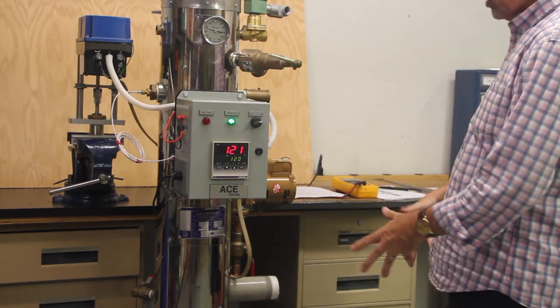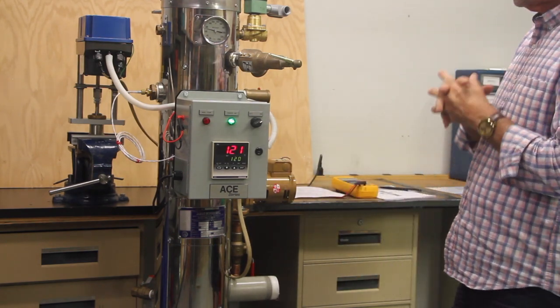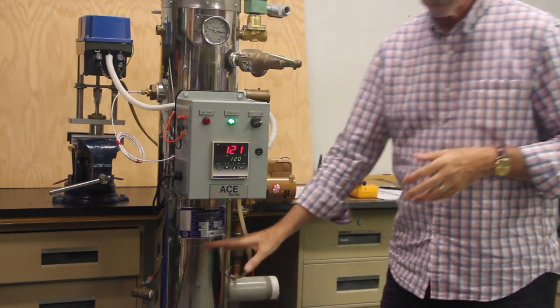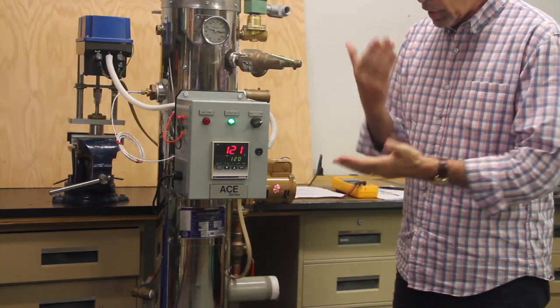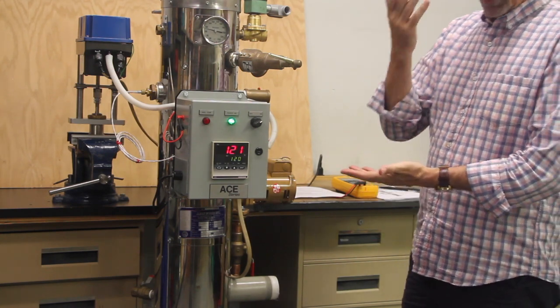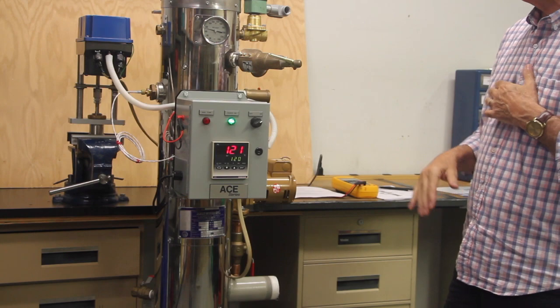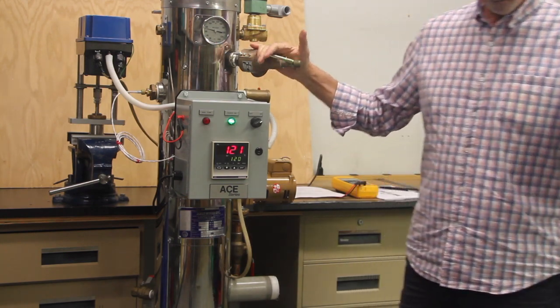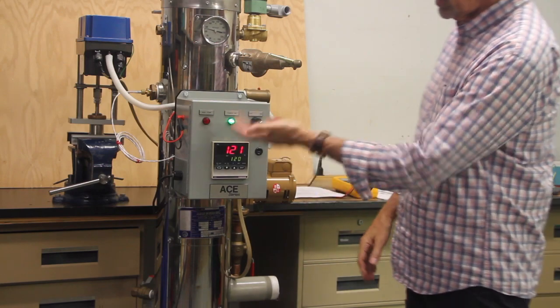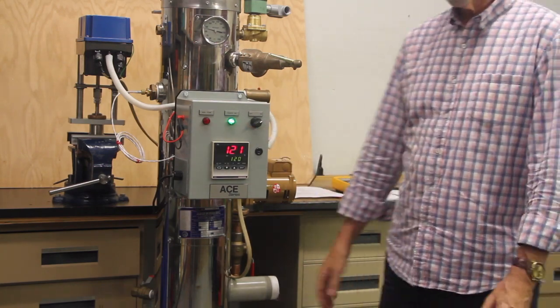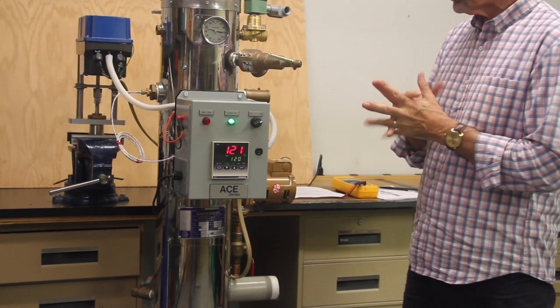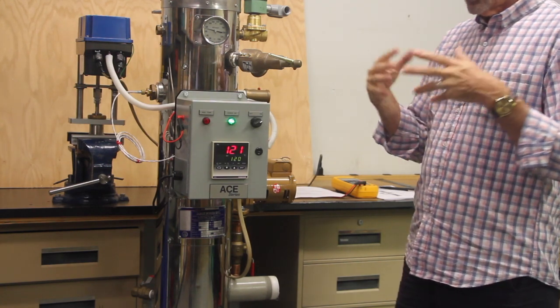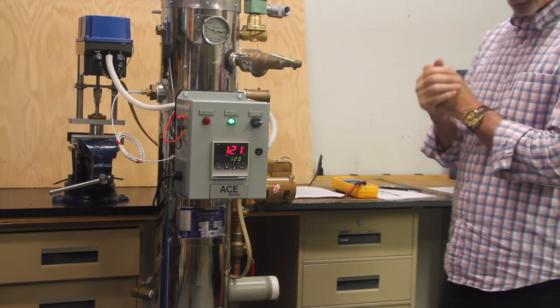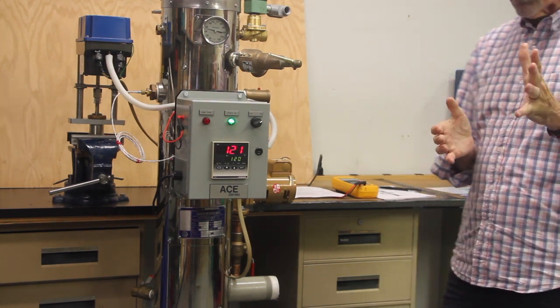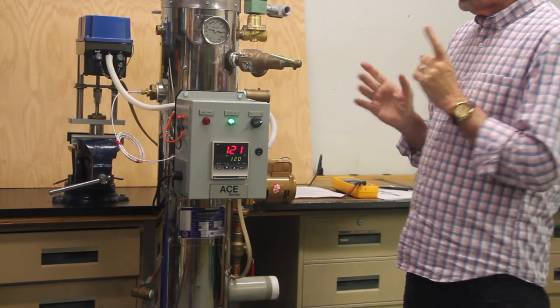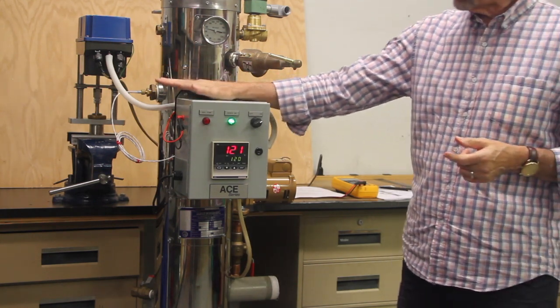You'll get an annunciation in your panel. The heater will shut itself down and turn itself back on, hoping that a piece of dirt got under the seat of the valve, and that by shutting down and opening wide open, it will flush itself clean and go back to normal. So you show up in the mechanical room and there's water all over the floor and the green light's on and everything seems fine. It's probably because a piece of weld slag or something got under the seat and it was bleeding BTUs when you had no load on the heater. This is common.